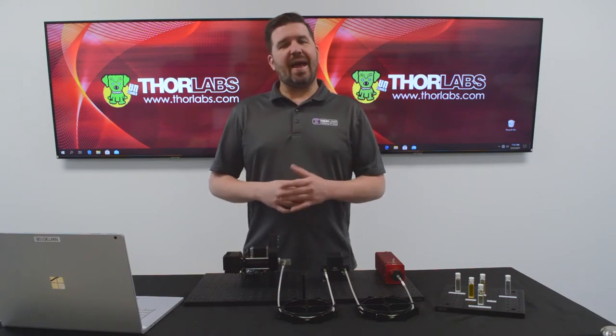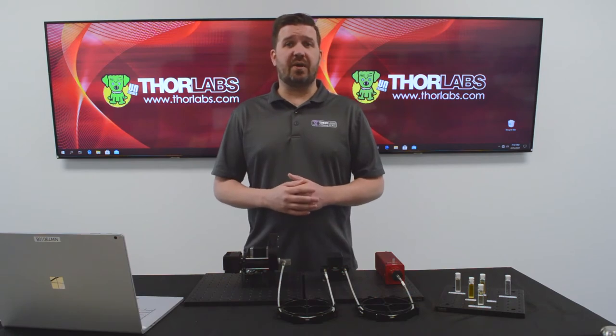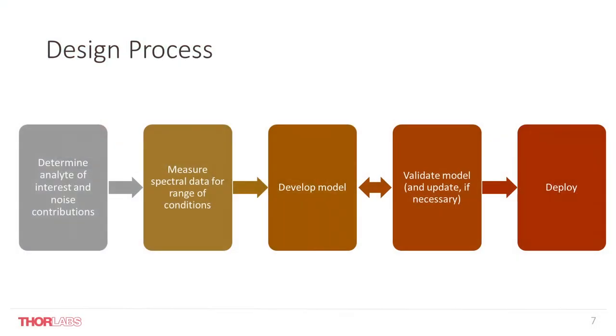Stepping back for a moment — how do we get from a concept to a system like this? It may be helpful to draw some parallels between how one would solve the problem with a traditional spectrometer. At the simplest level, the process may look like this: first, determine the desired chemicals or analytes of interest to measure, and any contributing components to our measurement, whether that be other analytes, measurement conditions, etc. Second, collect our spectral data. Third, develop a model to distinguish the analytes of interest. Fourth, test and update the model with validation sample sets. And lastly, build the system and deploy.